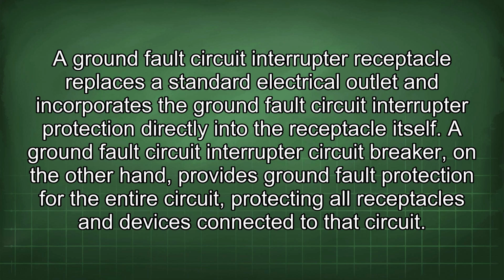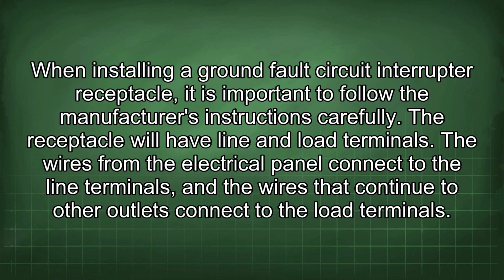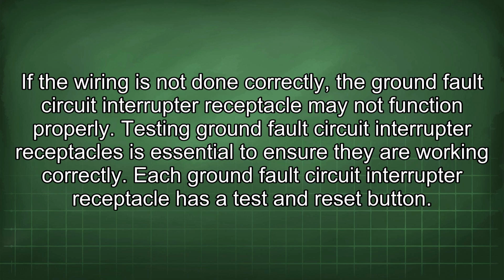A ground fault circuit interrupter circuit breaker, on the other hand, provides ground fault protection for the entire circuit, protecting all receptacles and devices connected to that circuit. When installing a ground fault circuit interrupter receptacle, it is important to follow the manufacturer's instructions carefully. The receptacle will have line and load terminals. The wires from the electrical panel connect to the line terminals, and the wires that continue to other outlets connect to the load terminals.